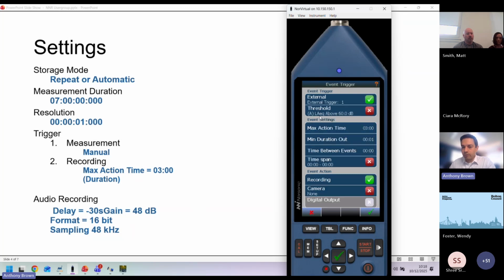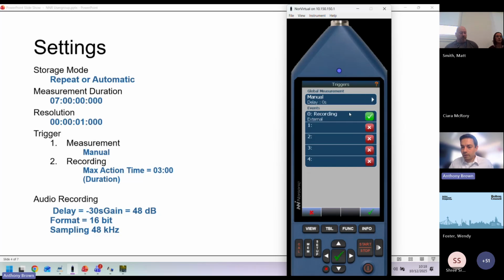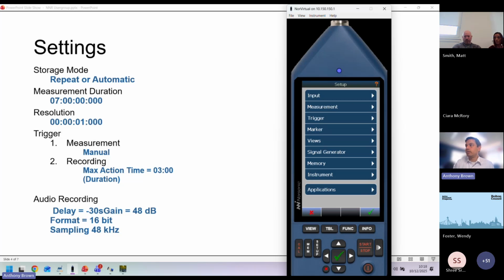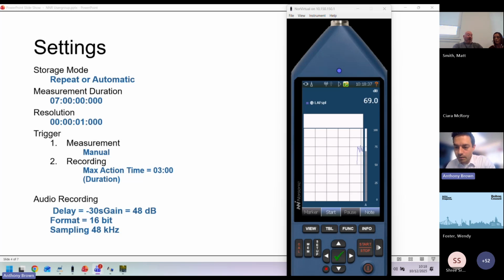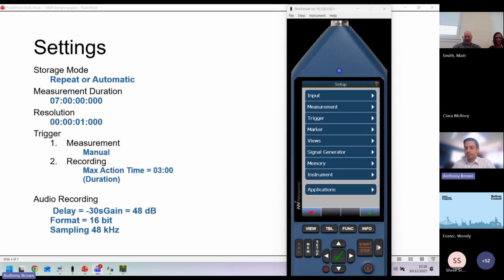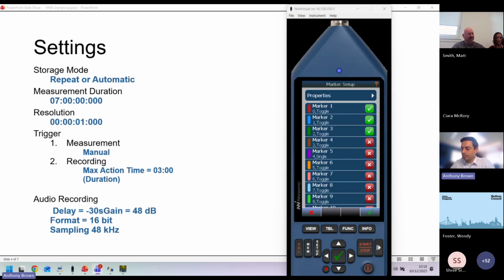If that doesn't say external, then you need to go back and just make sure this top one is ticked here. And this threshold is off. So this needs to say external. And then you would then press the tick on the bottom of the screen to go back, and then you should be back in the setup menu. If anyone's gone back to this screen, then just press this setup key to go back into the setup. And then we'll look at the marker. So this one here, marker.